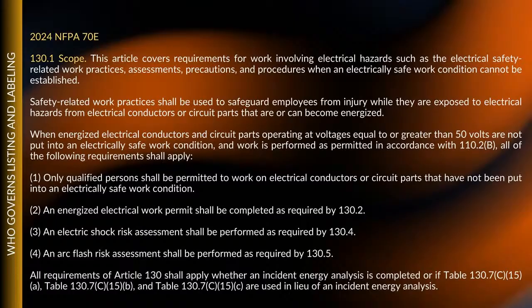Now this is where you want to pay attention, because watch what it has you do here, and then I'm going to explain how you do this. First and foremost, you put it in an electrically safe work condition if you can. If you can do that, there are certain things you need to do and certain ways to protect yourself until you verify it's in a de-energized state, because it's always energized until you prove otherwise. 100%. In other words, you're never planning on working on it energized. You're going to put it in an electrically safe work condition. The one reason you might not is that you don't have working clearances, or it's due to the type of equipment or whatever it is. Therefore, you have to do certain things to protect yourself from a shock.